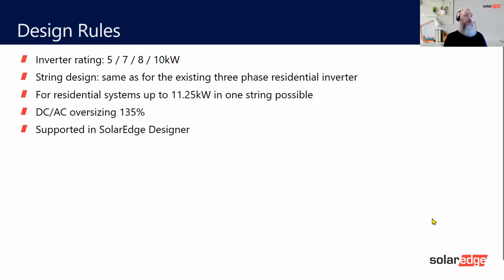Design rules are 5, 7, 8, and 10. The string design is exactly the same as a normal 3-phase inverter, 11.25 kilowatts per string, and the DC oversizing is 135%. So it's exactly the same as a normal inverter, it just allows you to have this. And it's also supported in the designer as well.